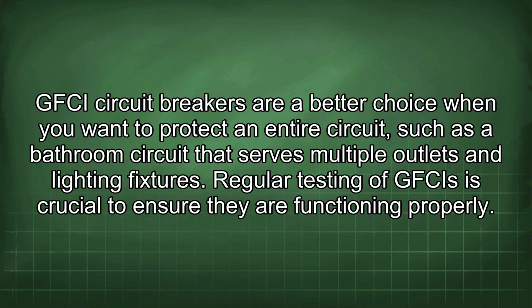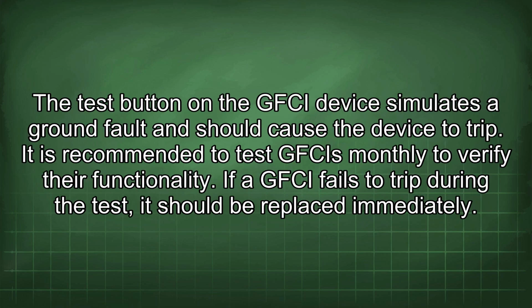Regular testing of GFCIs is crucial to ensure they are functioning properly. The test button on the GFCI device simulates a ground fault and should cause the device to trip. It is recommended to test GFCIs monthly to verify their functionality. If a GFCI fails to trip during the test, it should be replaced immediately.